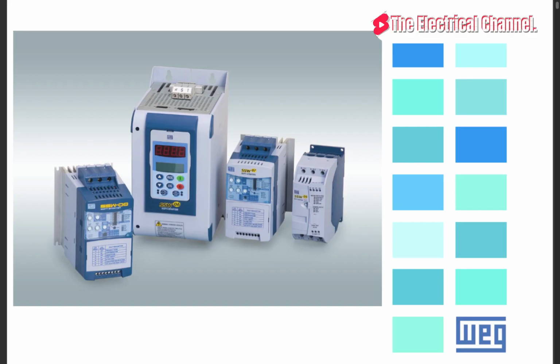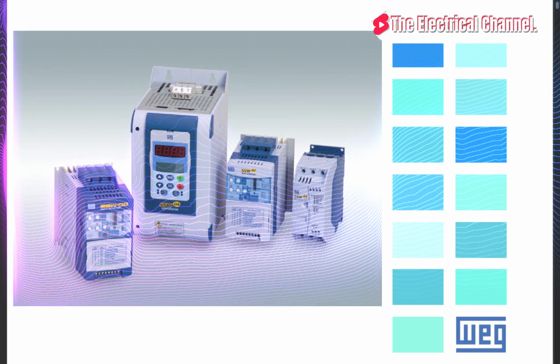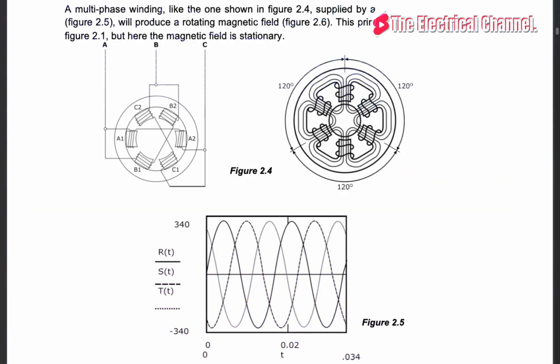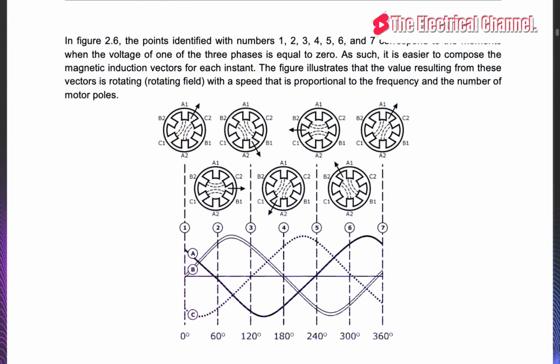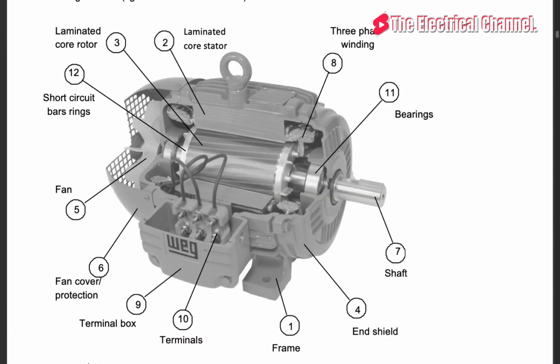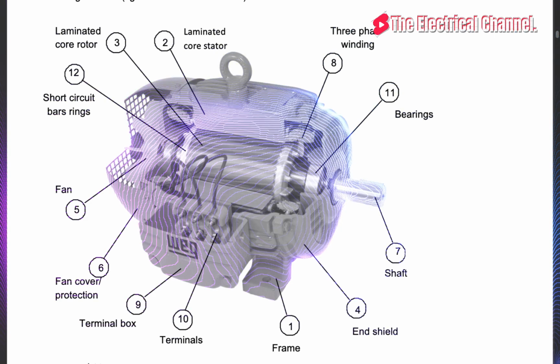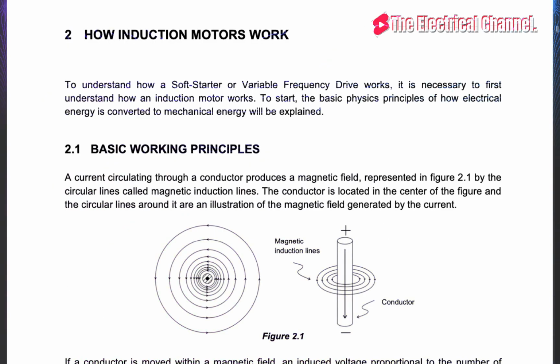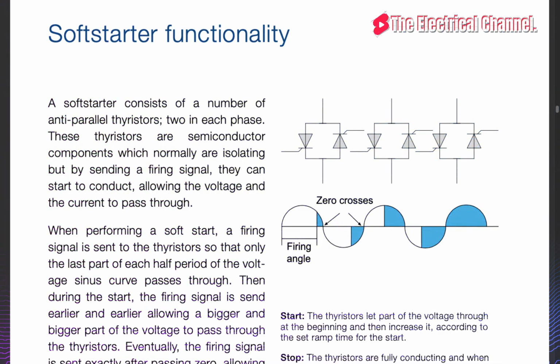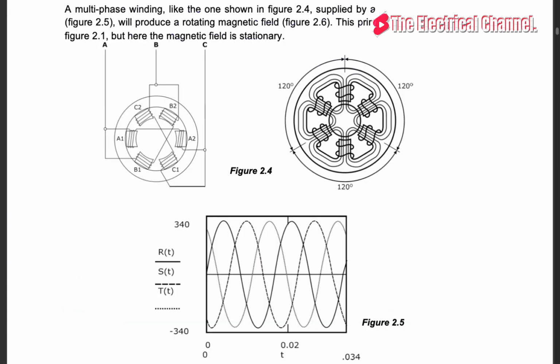without giving a start signal to the starter. This will not start the motor, but it would heat up the motor and eventually damage the motor. Even if a line contactor was to be used to avoid this during startup, the current will basically not be reduced at all when starting, and reducing the current perhaps is the most important benefit of using a soft starter.